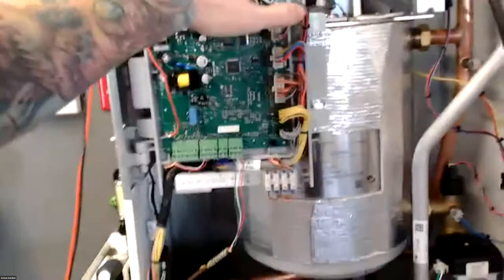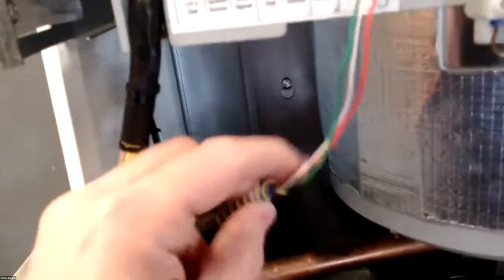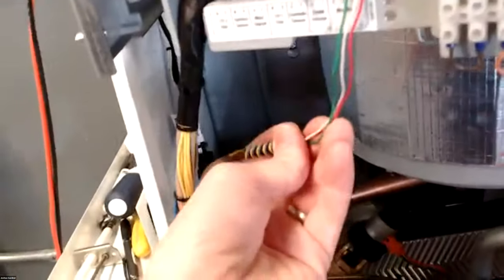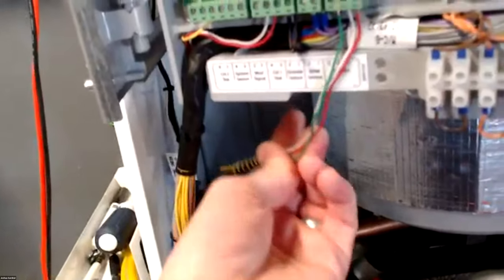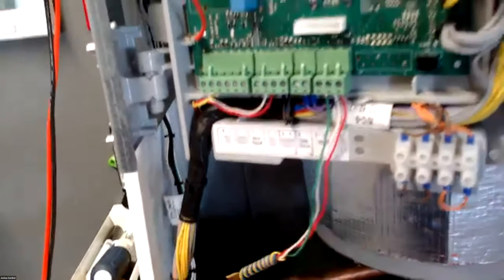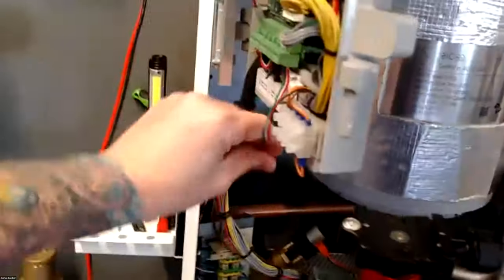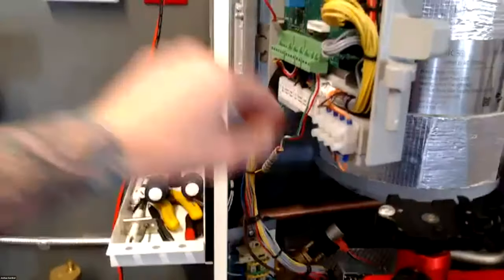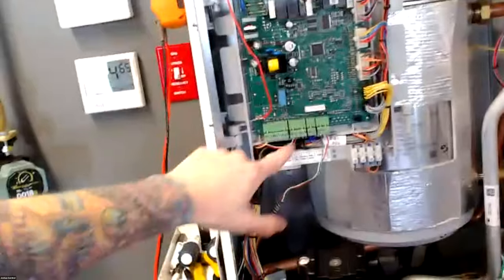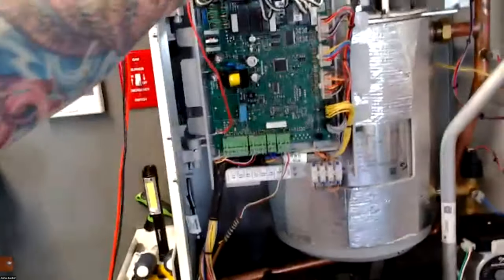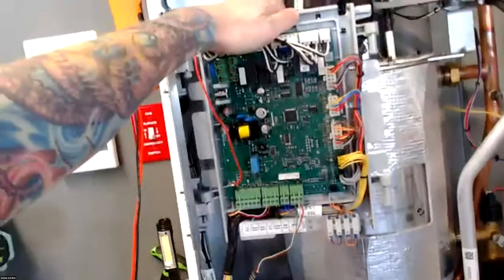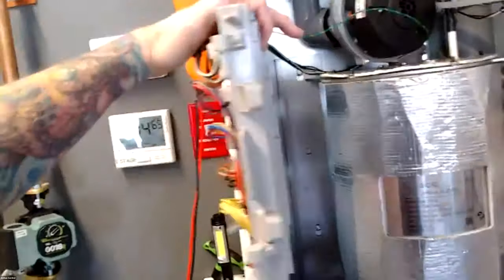When you're wiring your low voltage connections, all right, you're running a wire up and your lead length's on here. When you go to get your length of wire, move the control out. Then get your length of wire and cut it. I'll see you guys wire the control board up just like this, and it will be so tight in here with the wiring that they won't be able to swing this panel out. So if you swing it out and wire it, you know you'll have enough lead length to swing the control out.